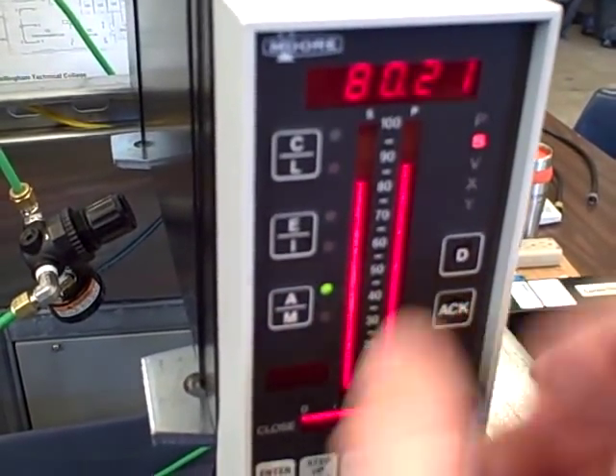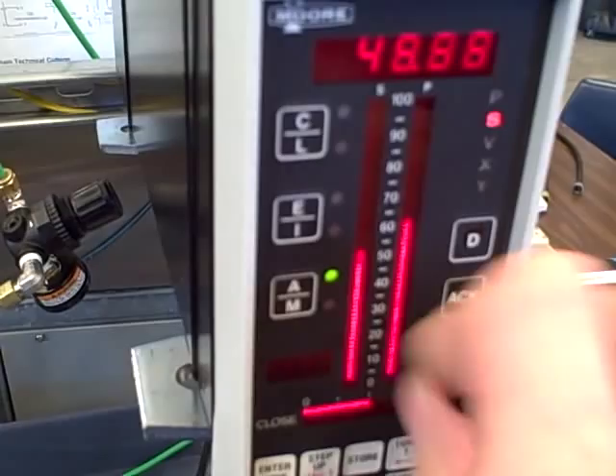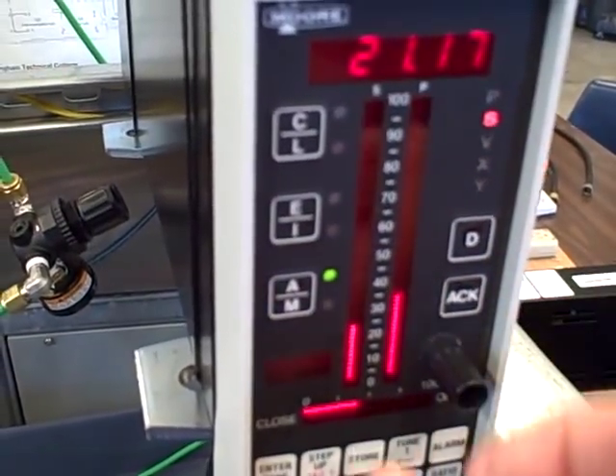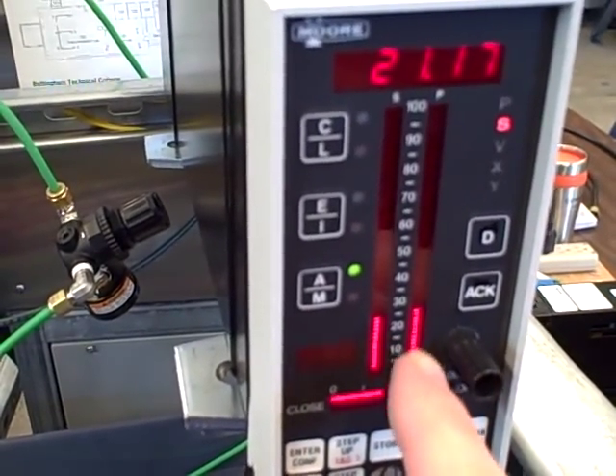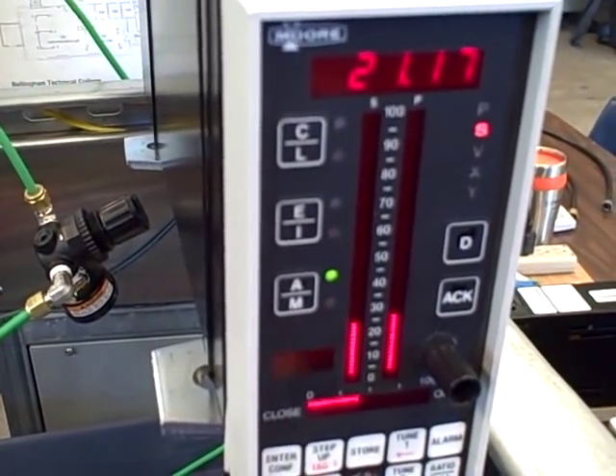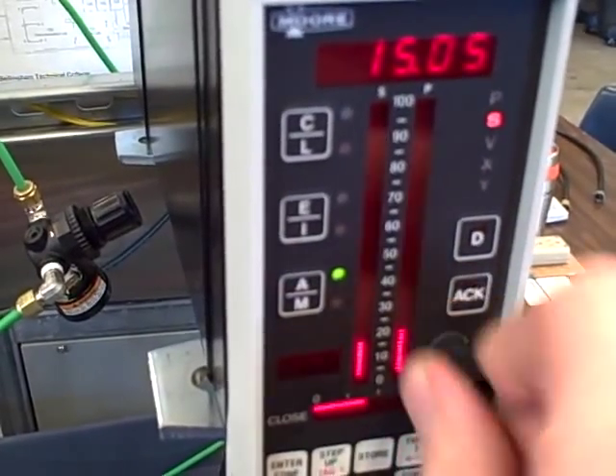Looking pretty good at the top end. If I turn it down, basically the same response. A little bit of offset here. Integral slowly takes care of that offset. But we don't have oscillation the way we had before.